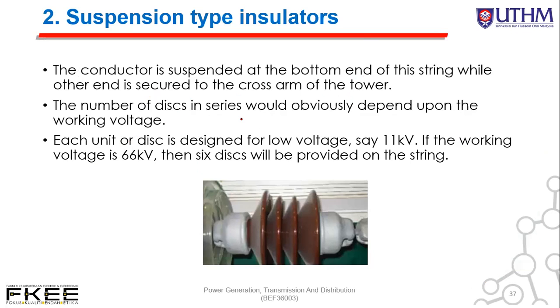The number of discs in series would obviously depend upon the working voltage. Each unit of disc is designed for low voltage. Setiap satu disc tu, satu porcelain tu, voltage dia adalah 11 kV only. So, if the working voltage is 66 kV, then 6 discs will be provided on the string. So, contoh ni ada 4, so maknanya 44 lah, 44 kV.